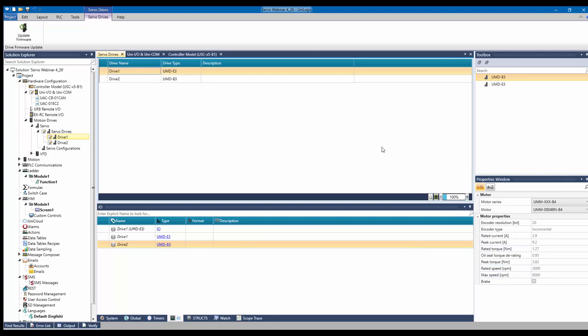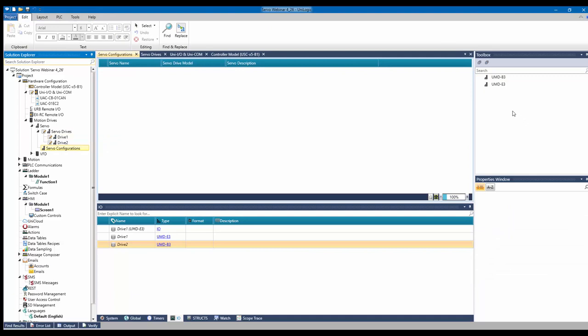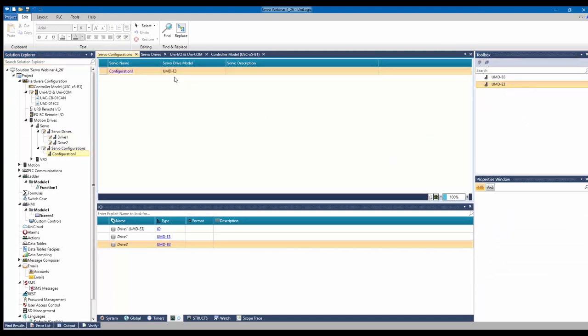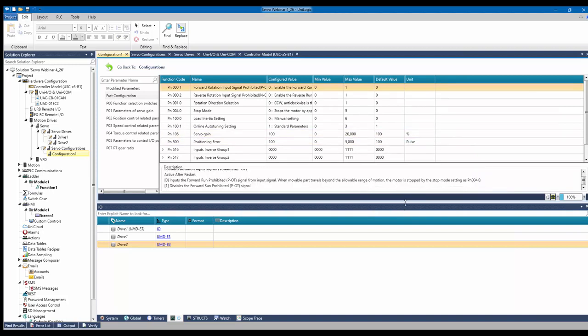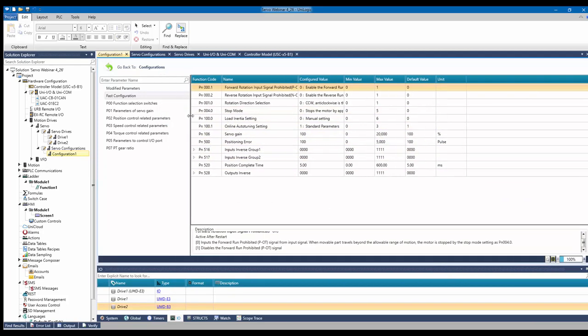The rated current, peak torque, rated speed, and everything populates directly into the software for calculations. Navigating to servo configuration for the EtherCAT motor — notice my servo model is added here. The configuration file saves directly to the PLC with no need for external storage. There are many parameters available on the drive: manual tuning, acceleration, deceleration speeds, torque limits, max limits — everything available on the drive is accessible here in the configuration.